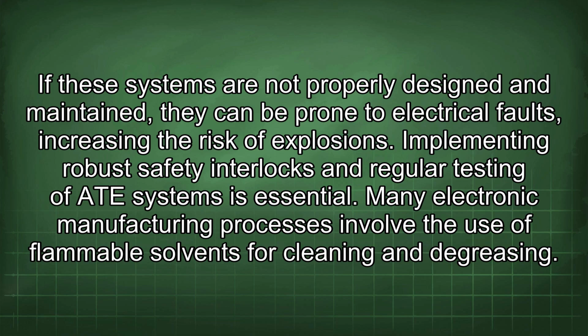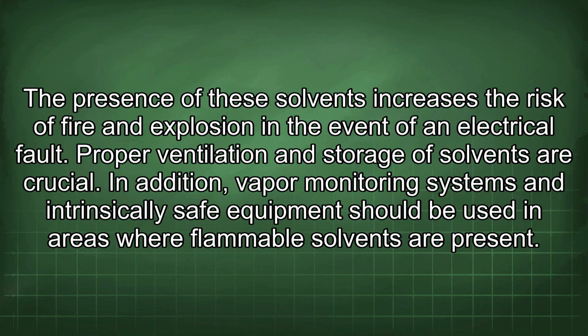Many electronic manufacturing processes involve the use of flammable solvents for cleaning and degreasing. The presence of these solvents increases the risk of fire and explosion in the event of an electrical fault. Proper ventilation and storage of solvents are crucial. In addition, vapor monitoring systems and intrinsically safe equipment should be used in areas where flammable solvents are present.